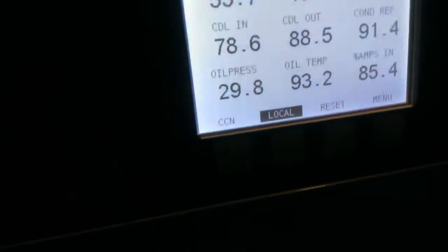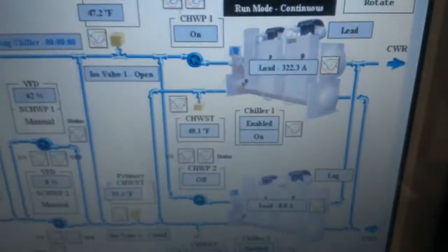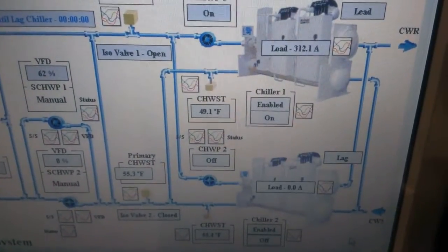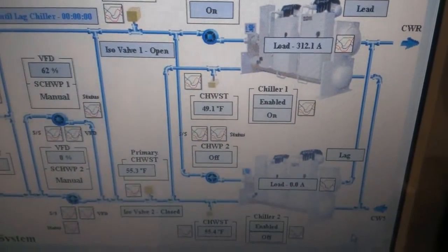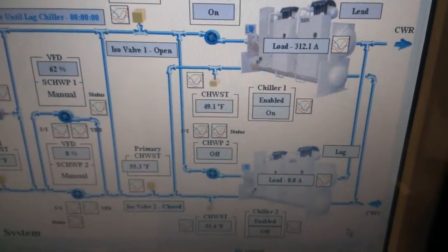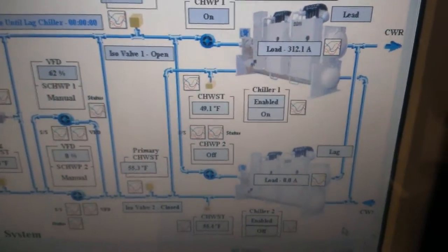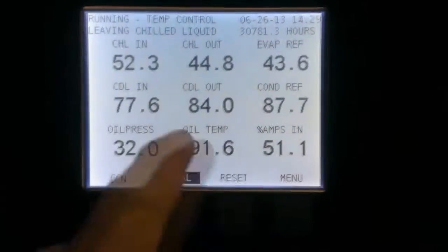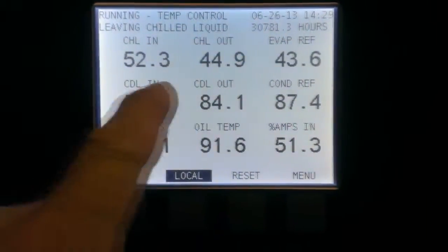Might be kind of leveled off right there. 85%. Let's see what the amps are. Man, this has got to be a lot. This unit hardly ever gets that high, unless you've turned it off. We started it and we had to catch up. Oh yeah, 322 amps. I think it dropped down 312. So it's pretty loaded up there.